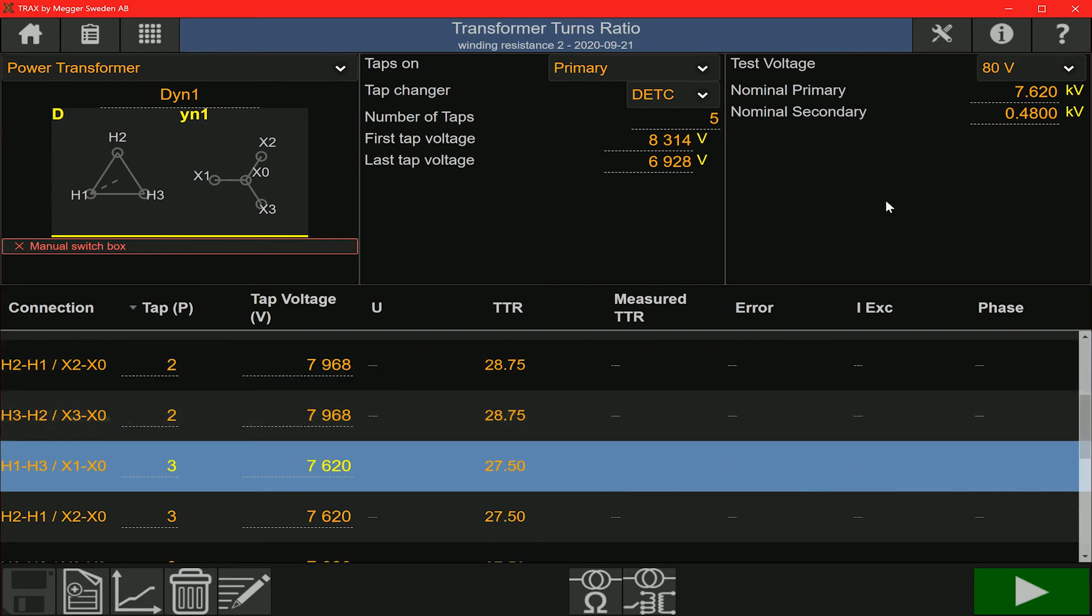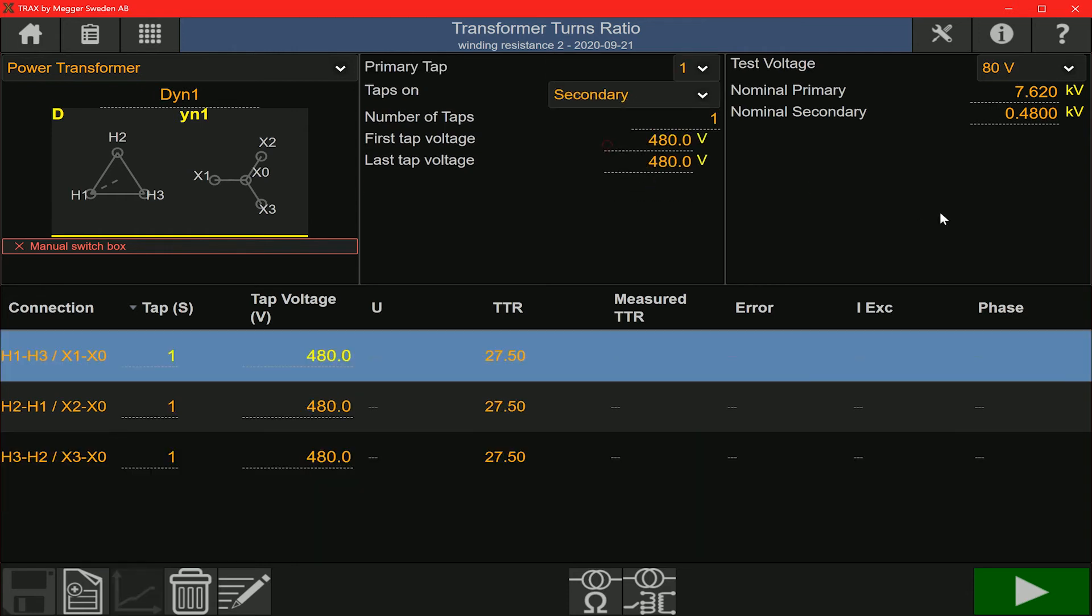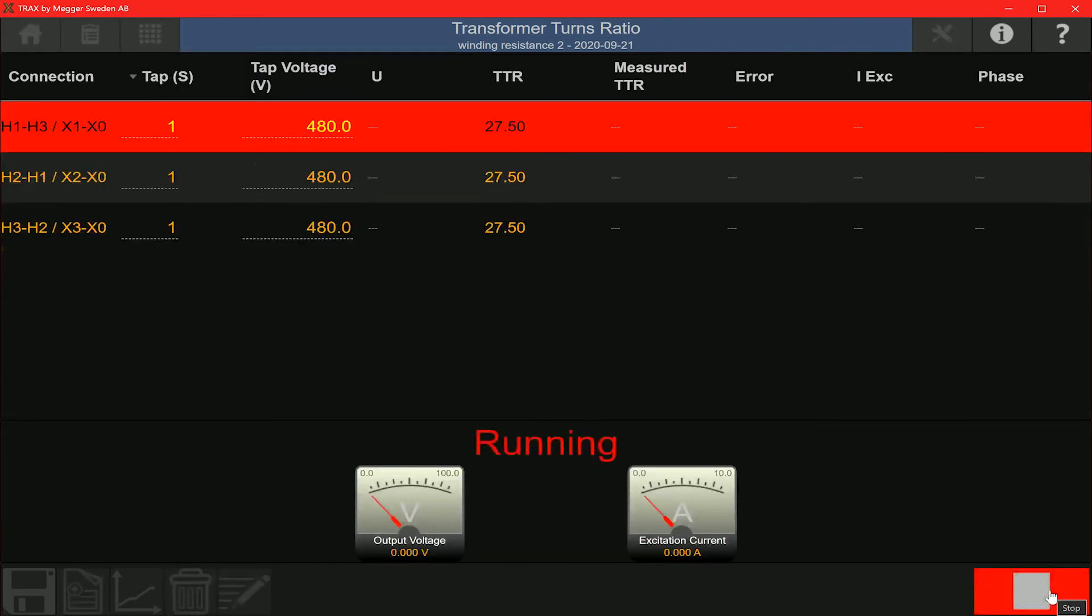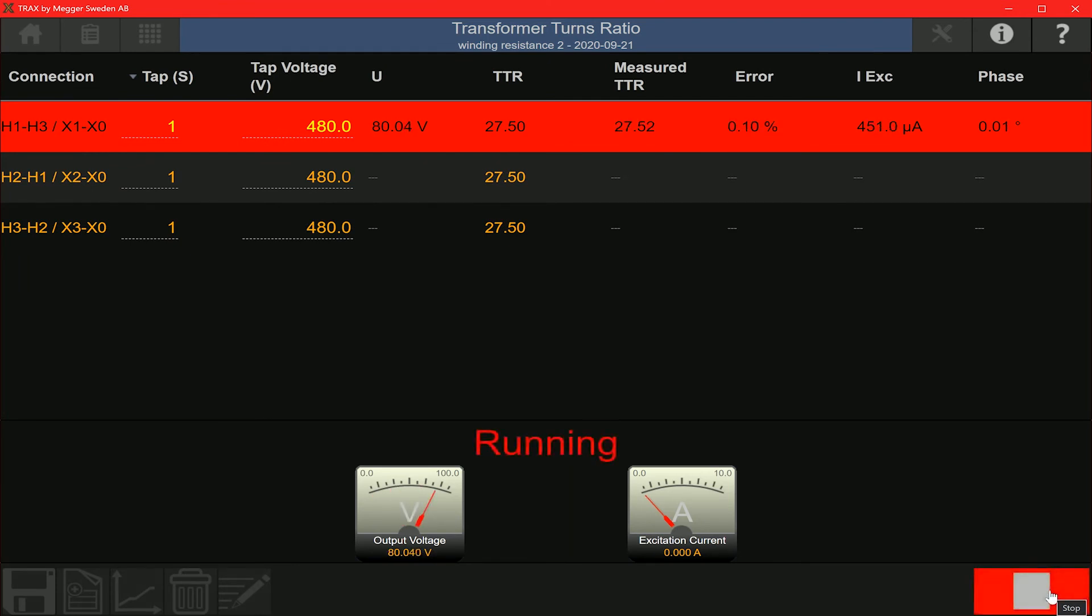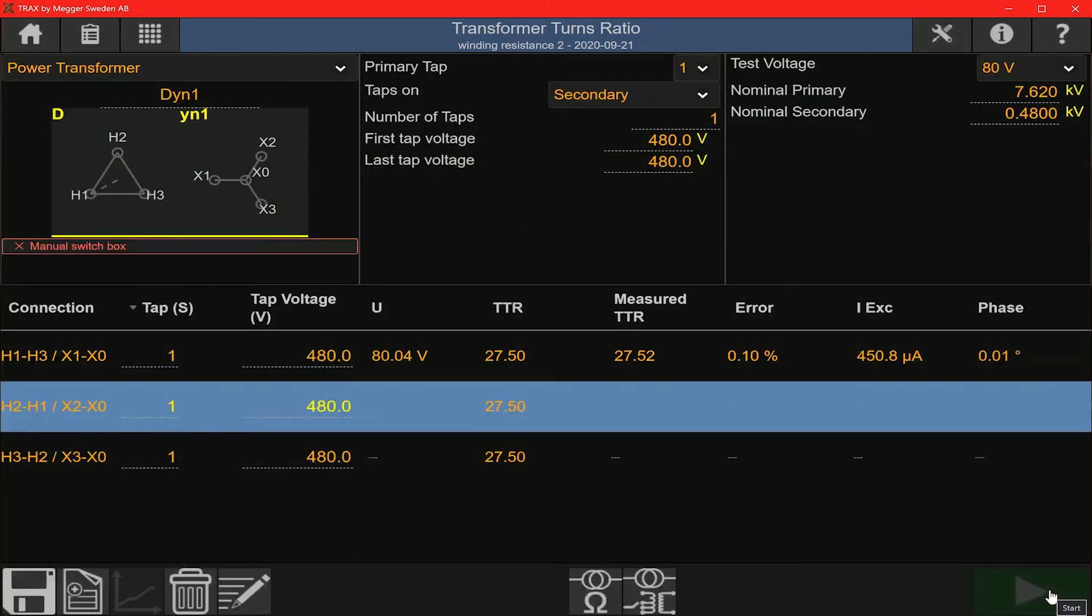I could either run the test on tap position 3 on this particular screen or I could just switch to the secondary. Since I'm testing on the nominal tap, I could do it on either screen. If I was testing on a tap other than the nominal tap, then I would only be able to run this correctly on the primary test screen. So this is our measurement on phase A, the first measurement. You can see the values populating there on the test screen. And at the end of the measurement, we get the TTR.